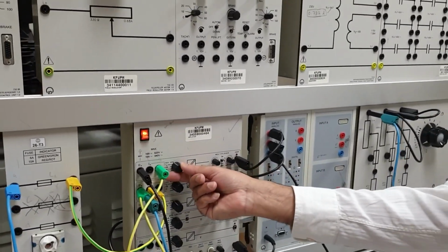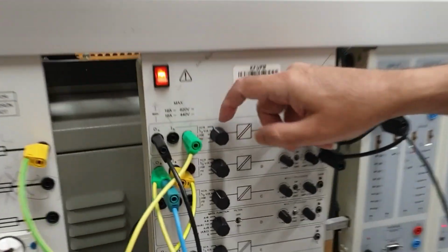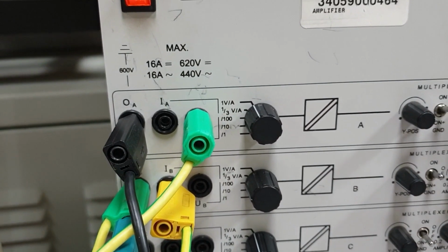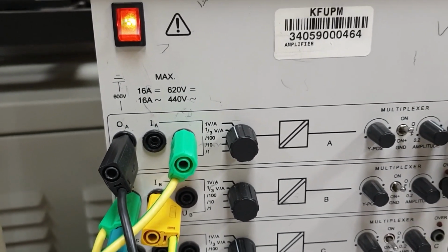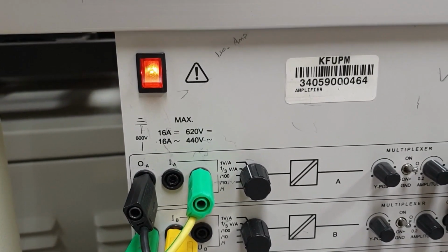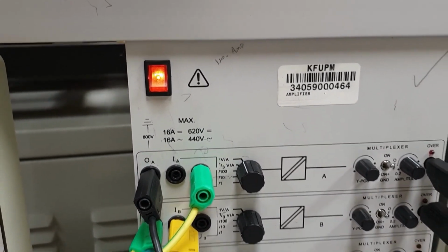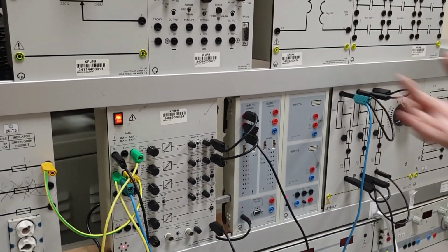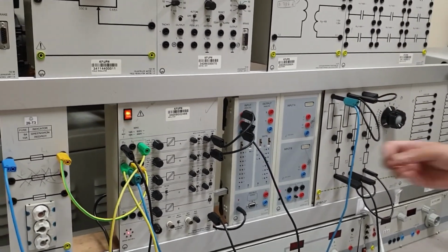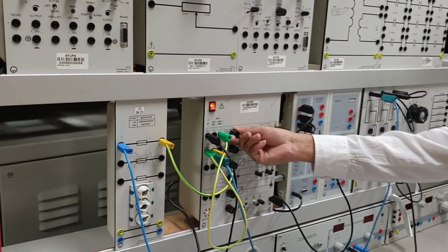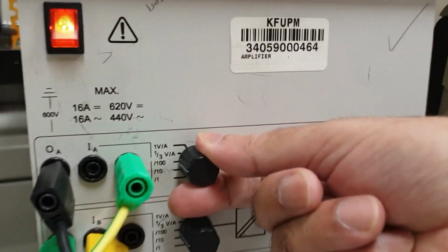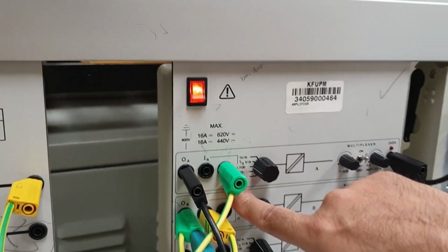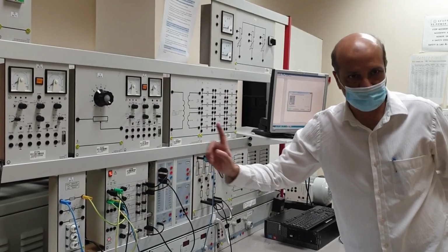You see this switch here? It's a selector switch, 1V over A, 1 by 3VA divided by; this is basically to attenuate the signal. That means we don't want the full voltage to pass through the equipment. We want to bring it down, in the case of the voltage. Otherwise, the design of these components will be very bulky, very large. It will not be as simple as that. So in the case of the voltage, we put this at divided by 100. You see, we are connecting to the voltage U. Whenever you connect to the U, it means we are measuring voltage from that channel. We are measuring 2 variables here, one voltage and one current.